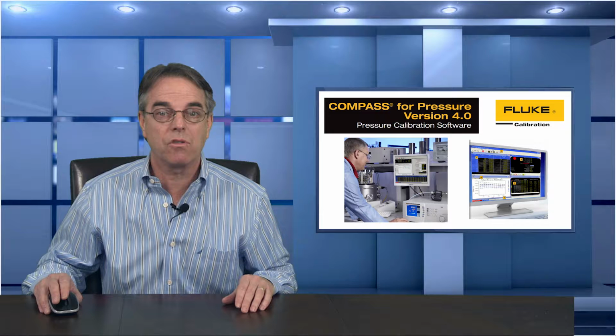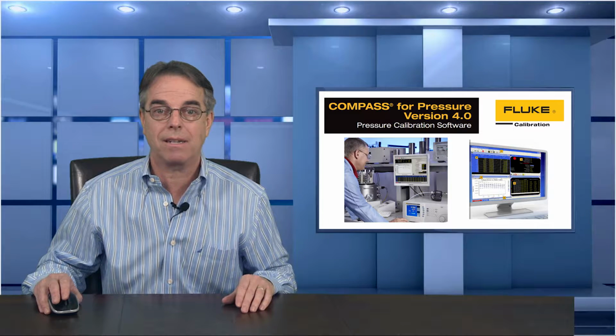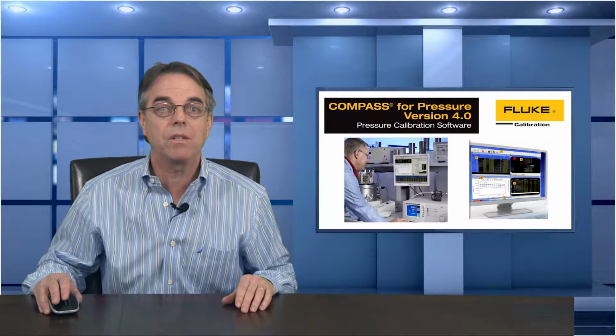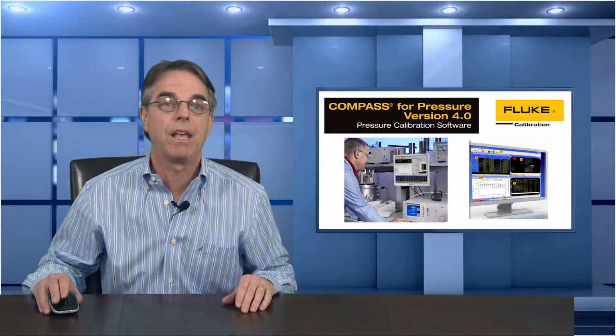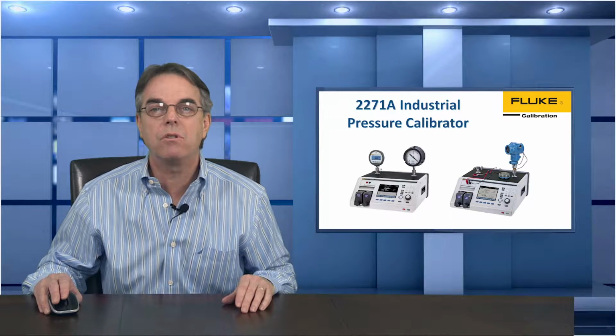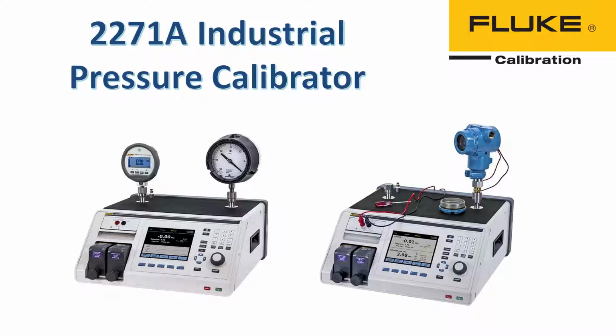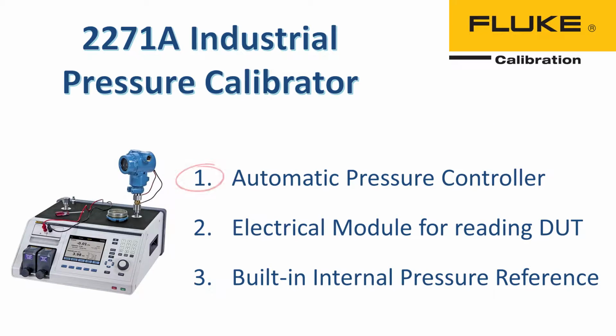However, it's definitely possible to automate some portion of this data collection process without using a computer at all, and in this week's video I want to show you a great example of that. In episode 2 of Calibration TV, I introduced you to the Fluke 2271A Industrial Pressure Calibrator. This unit is part of a growing number of devices that help us satisfy all the criteria we need to automate our calibrations. It can automatically change our stimulus because it's an automatic pressure controller. It has an electronics module to read the output of our test device, if that output is either current, voltage, or HART communication. And the plug-in pressure modules act as our pressure reference value.